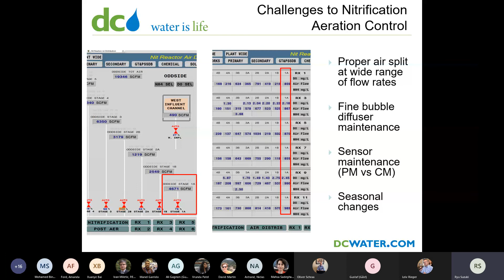And finally, for the sensor maintenance, we have implemented a lot of the preventive maintenance program to really stay on top of it. But at the same time, our I&C staff have to maintain an incredible number of equipment out there. And if there's other, more process critical equipment that pulls them away, then maintaining these sensors gets put on the back burner. It just becomes easier to put them in manual and have a constant control and forget about the more advanced control, because we could get away with it for this particular process area. But for other process areas, such as thermal hydrolysis, you cannot get away with any kind of faulty sensor or control equipment. So those would take priority.